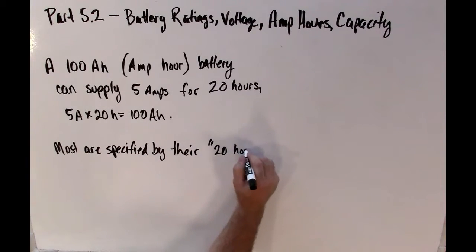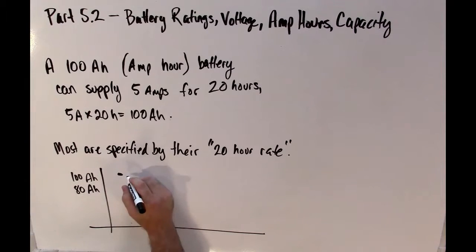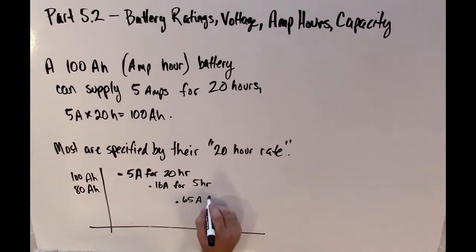You might be tempted to think that 20 amps for 5 hours would also be another way to get 100 amp hours, but it turns out that the battery capacity itself changes depending on the discharge rate. So the 20 hour rate is sort of a standard rate, so you'll find batteries for sale and the discharge rate is a 20 hour rate.